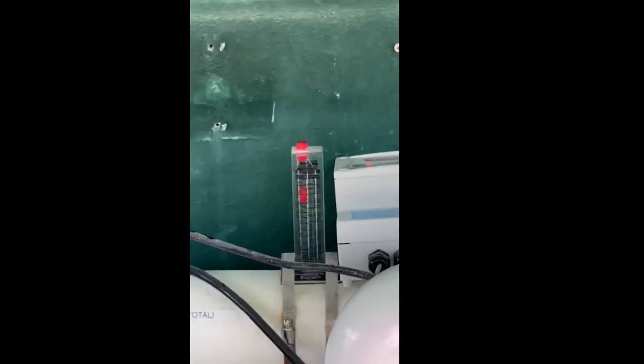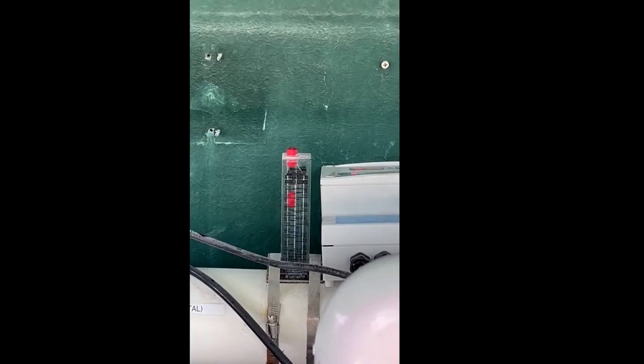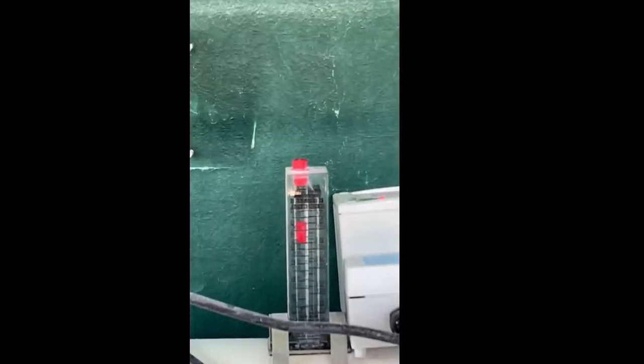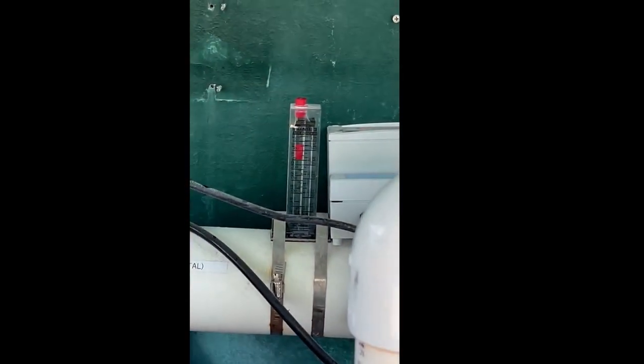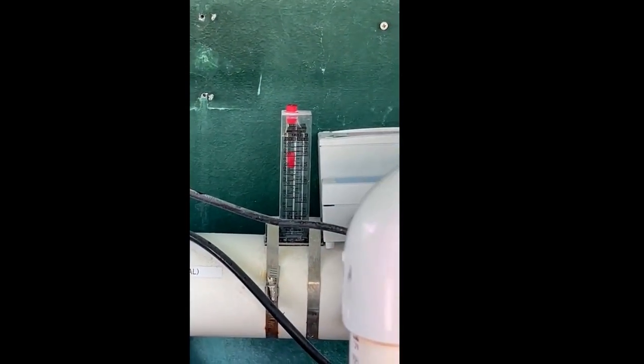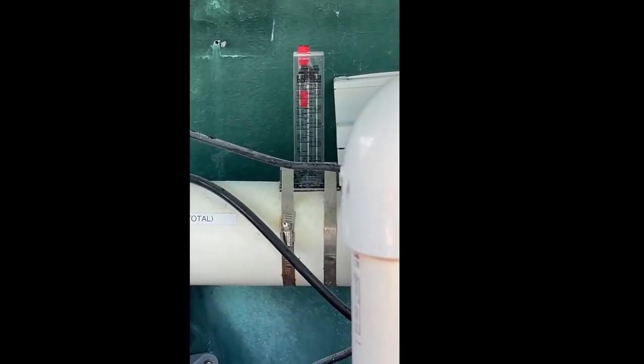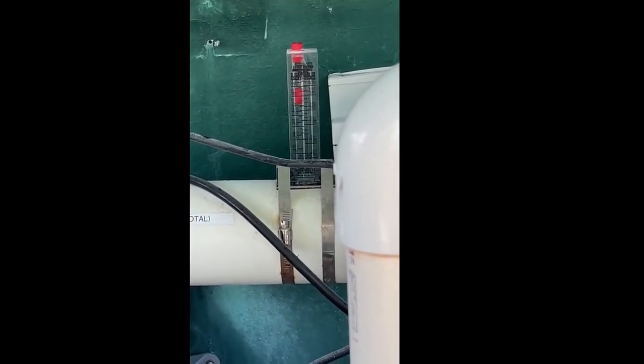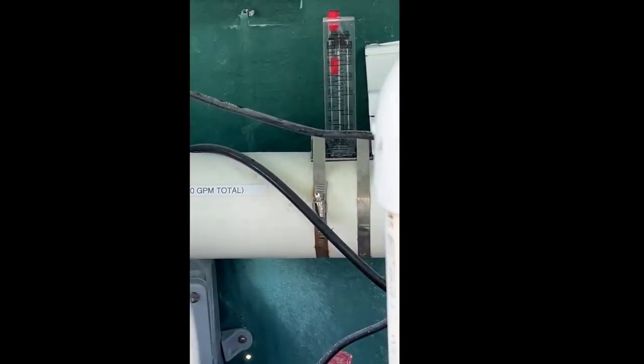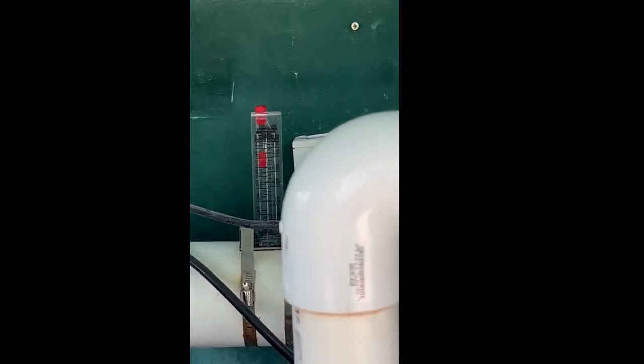This is the most important piece right here. Pay attention, pay attention. This is the flow meter. This indicates the flow of water. We are at about 300 gallons per minute. Ideally, and that red thing bobs up and down. You can see it, the red little thing, it bobs up and down, right? If that's low, that indicates a flow problem. Typically, the filters need to be cleaned, okay? Or a valve is not open fully. You want to see it bursting through the roof, ideally. That indicates good flow. This is the first thing the health inspectors look for when they come to check a property.